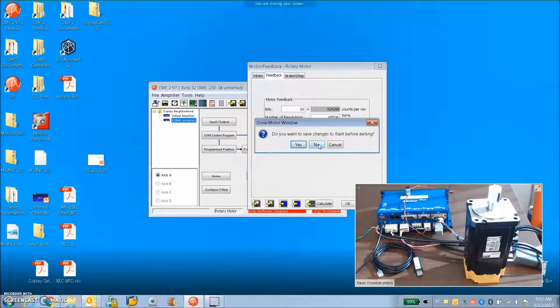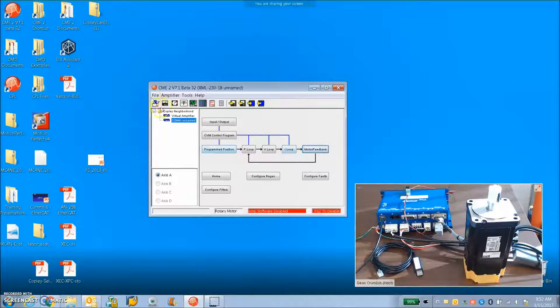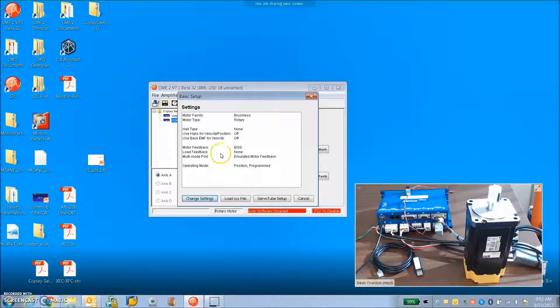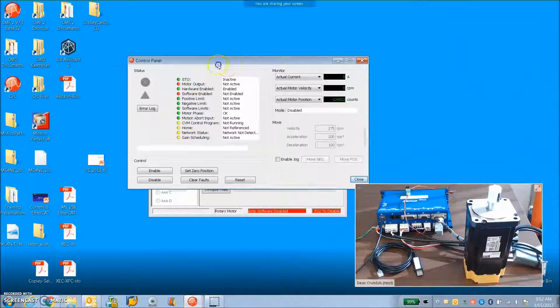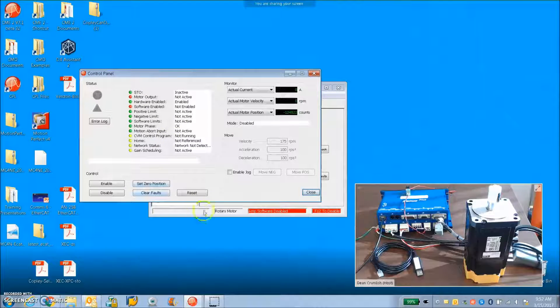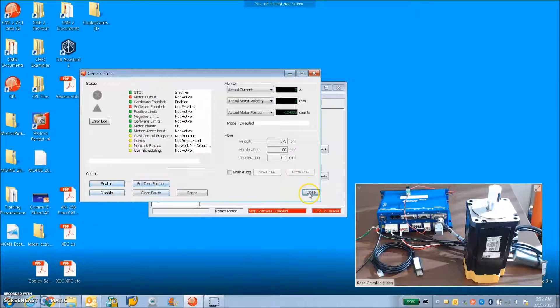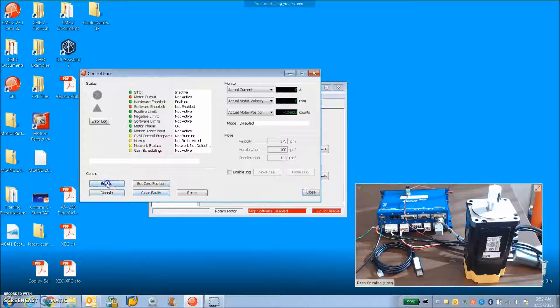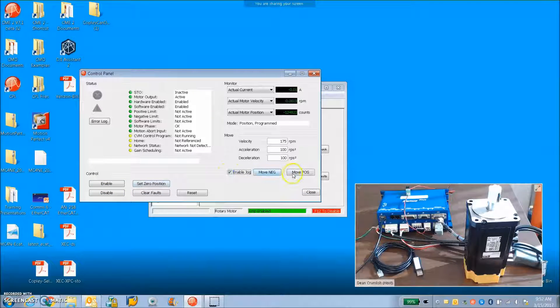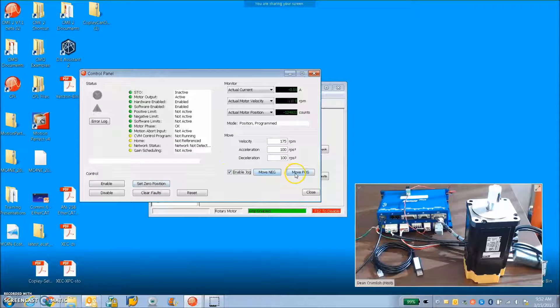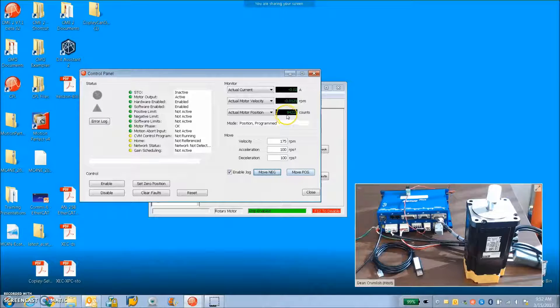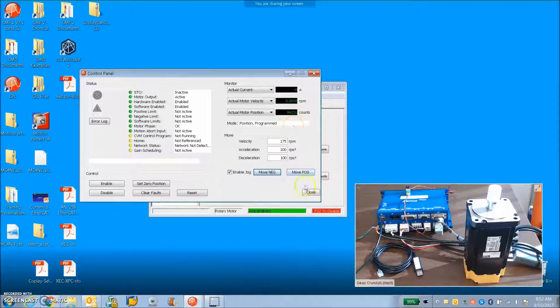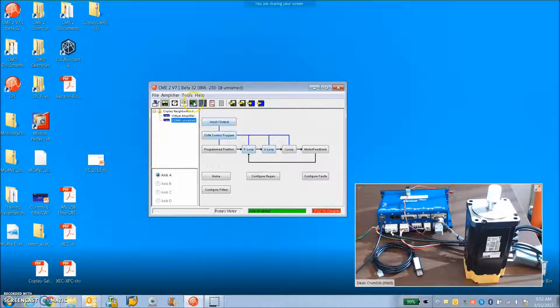We can calculate the initial tuning values. I did notice that the velocity gains were a little high, so I had to turn those down a bit. But normally from calculated values, we can rotate the motor shaft and we can see the actual position from power up.